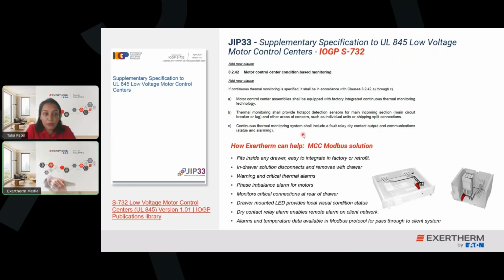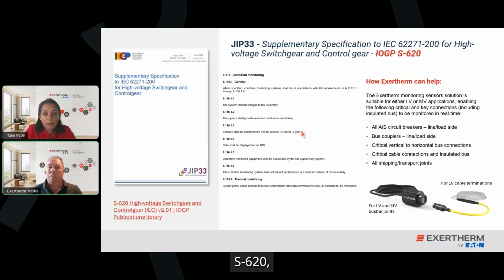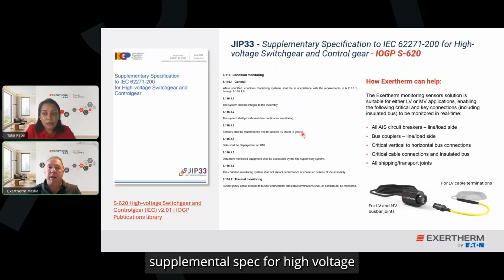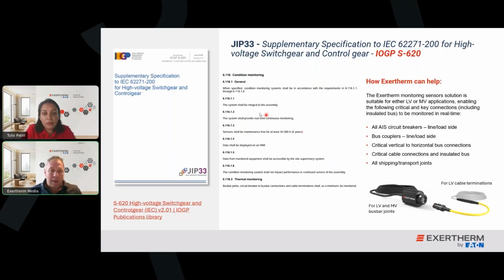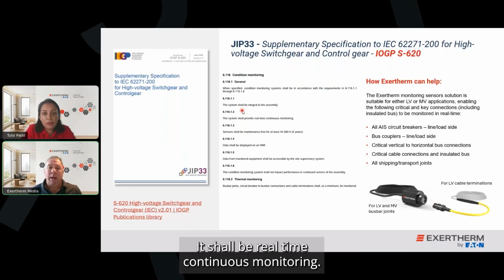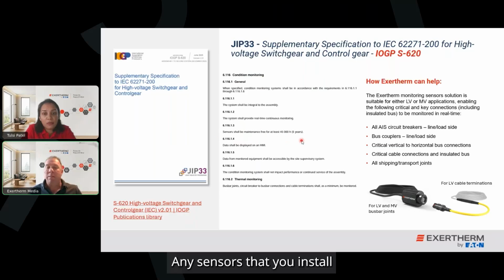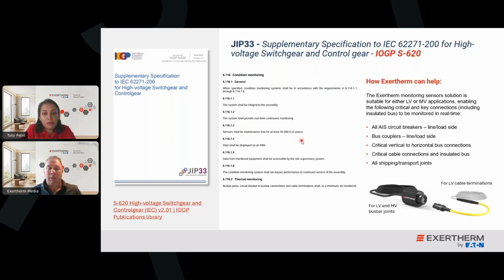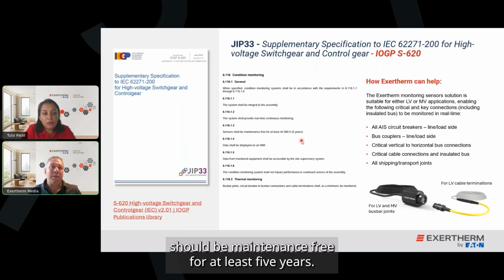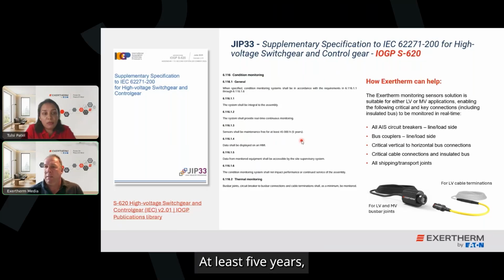S620, supplementary spec for high voltage switchgear and control gear. Again, it puts up condition monitoring. It shall be integral to the assembly. It shall be real-time continuous monitoring. And I think this is quite an important point here. Any sensors that you install should be maintenance-free for at least 5 years, and even longer if possible.